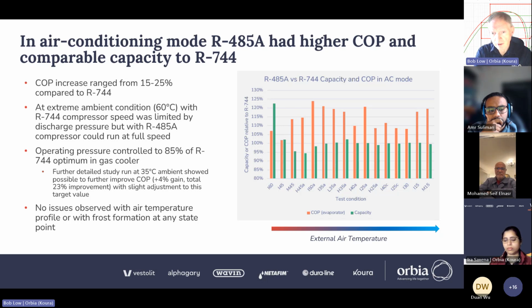The bar chart shows the performance points in terms of capacity or COP in relation to the measured CO2 values. There's a whole load of points there, but basically, if you want to get a shorthand feel for it, the highest air temperatures are on the left and the lowest air temperatures on the right. And the numbers along the bottom denote the air temperature onto the gas cooler, or the outside air temperature, if you like, going into the system. So 60 C is the hottest temperature, that's on the left. And then on the right, we have 15 C.